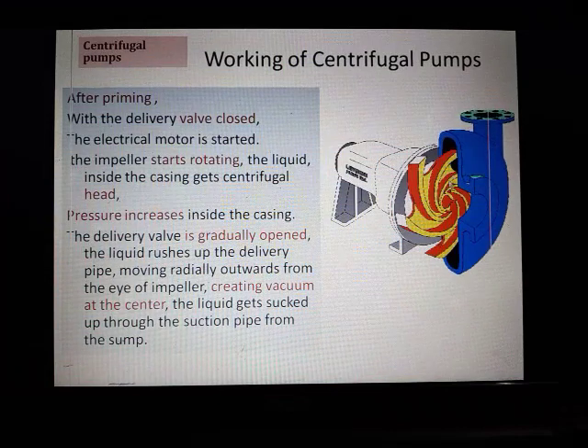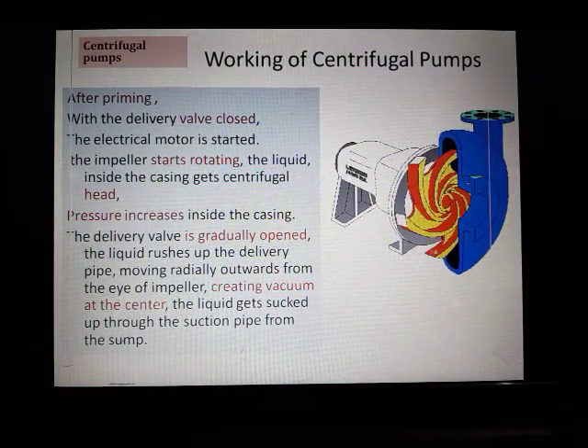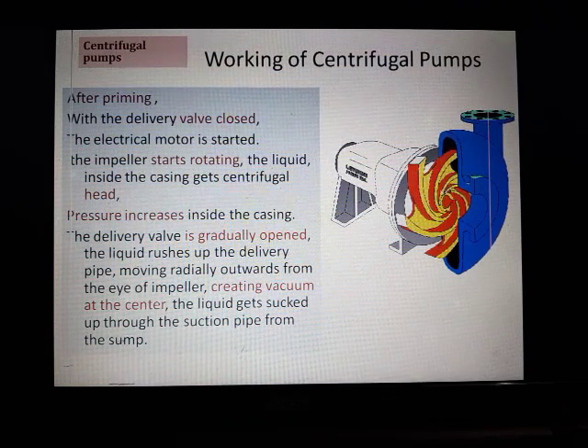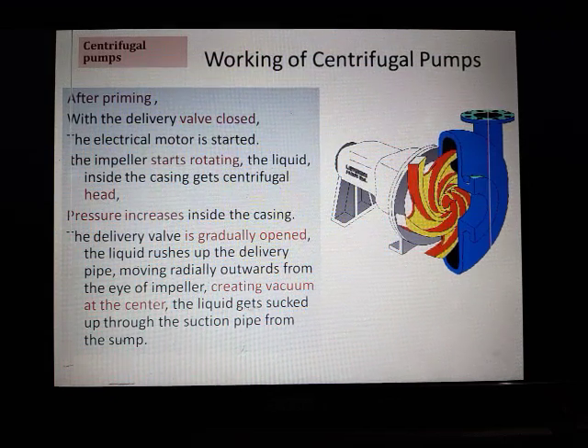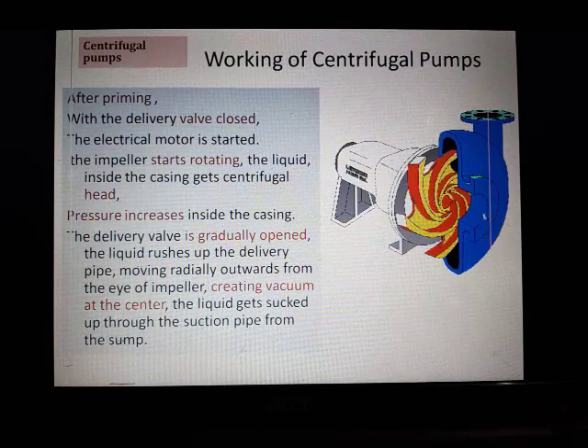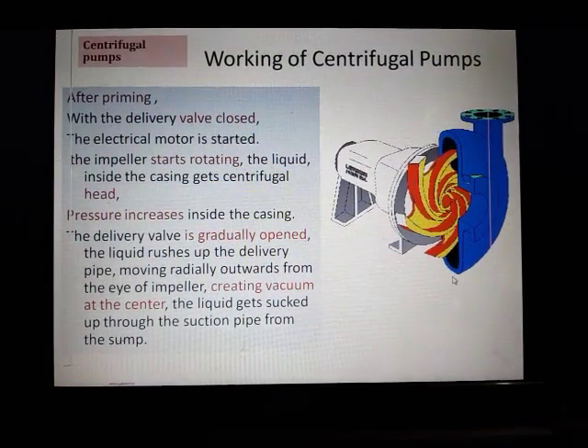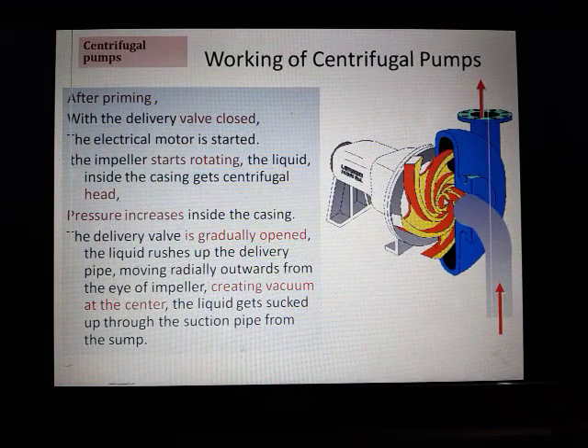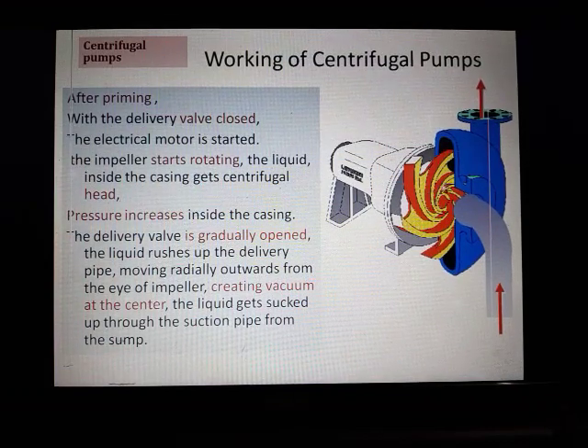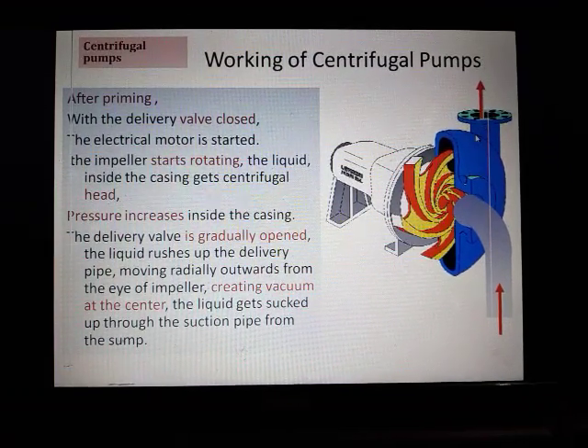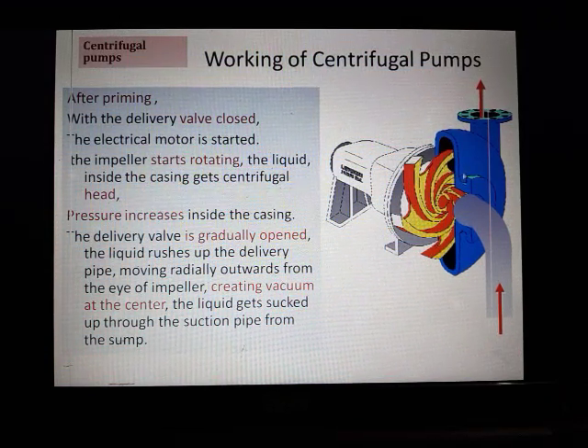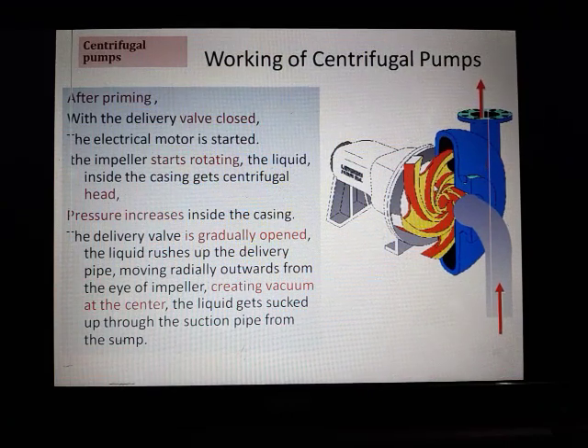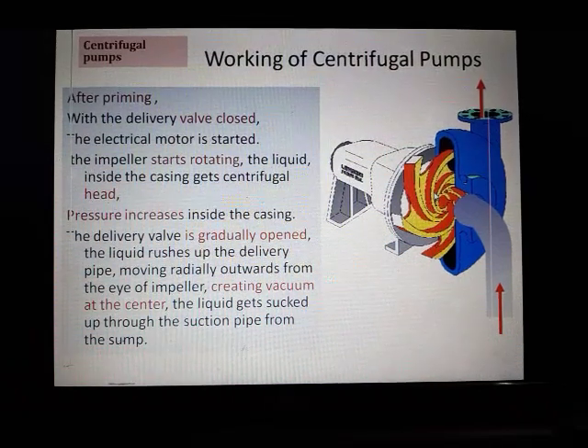Once the liquid starts rising up, water is thrown out of the vanes radially away from the centre. This creates a vacuum at the centre, and the liquid gets sucked up through the suction pipe from the sump. Once there is a vacuum, water enters continuously. Whatever water enters gains energy and tries to go up the delivery pipe — that is how it continues. Without priming, this suction would not happen, which is why it is essential that pumps are primed first and then started.